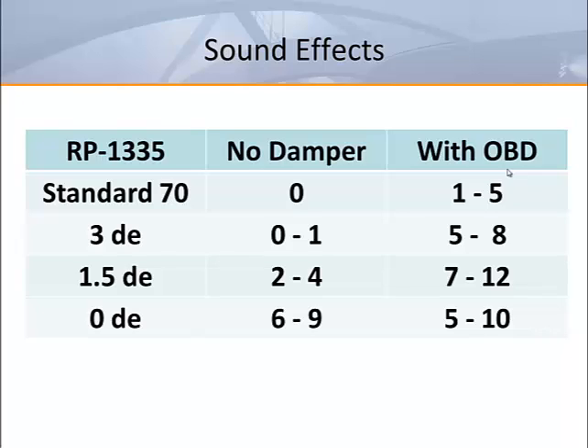Under laboratory conditions, adding a damper added up to 5 NC. With 3 diameters of straight duct, the sound was just slightly higher than laboratory or catalog conditions. At 1.5 diameter equivalents, the sound increased by 2 to 4 NC, plus another 5 when the damper was installed in the inlet. With a hard 90-degree elbow on the diffuser, the NC increase to the catalog was 5 to 10, but the damper did not create any additional noise.